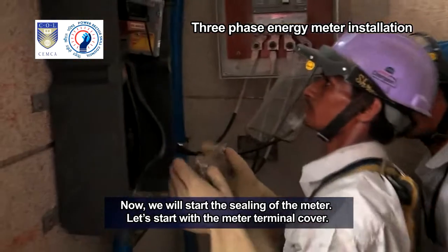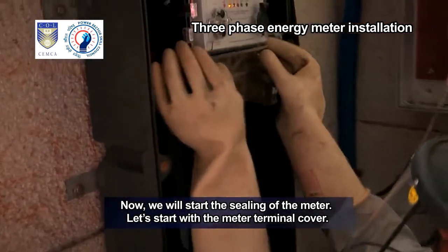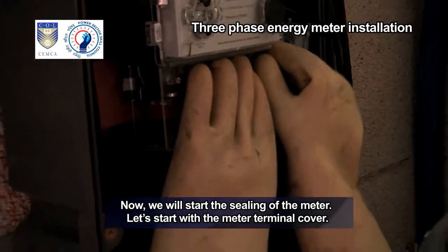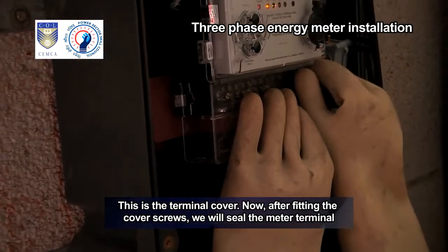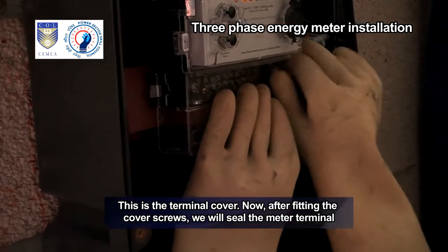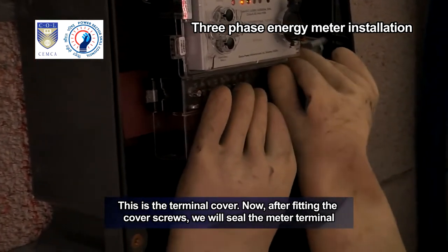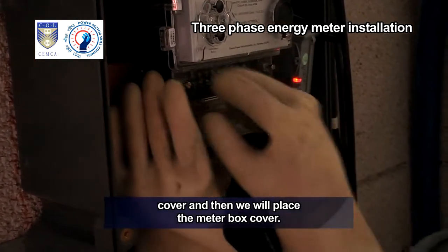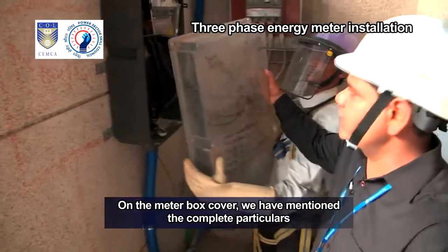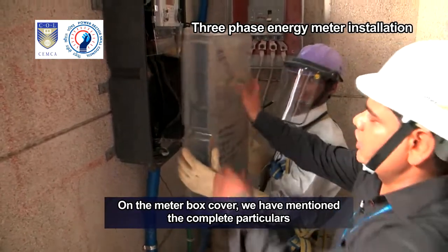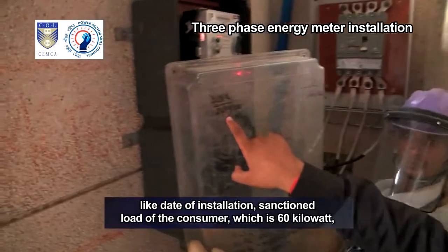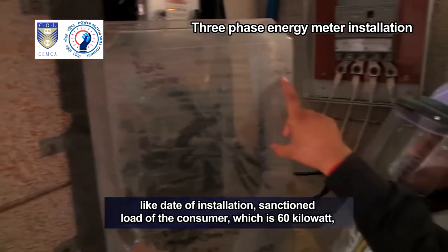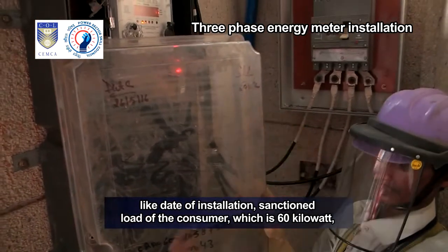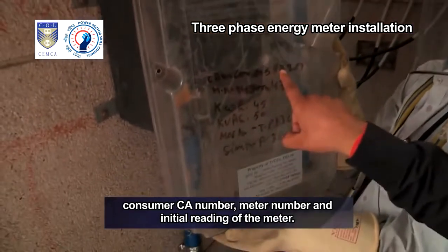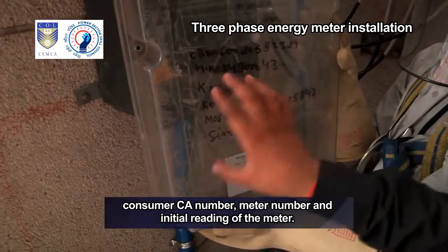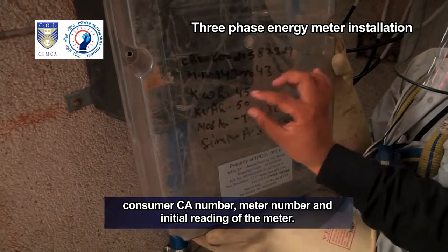Now, we will start the sealing of the meter. Let's start with the meter terminal cover. This is the terminal cover. Now, after fitting the cover screws, we will seal the meter terminal cover and then we will place the meter box cover. On the meter box cover, we have mentioned the complete particulars like date of installation, sanctioned load of the consumer, which is 60 kilowatt, consumer CA number, meter number and initial reading of the meter.